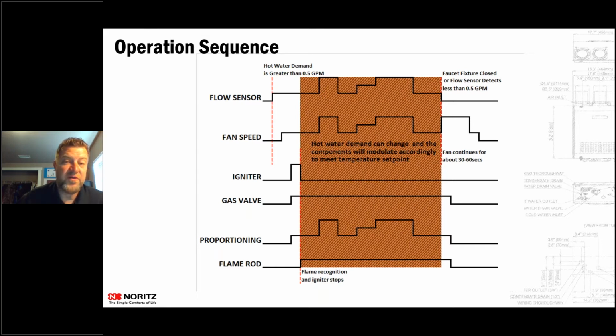tankless needs about a 30-degree differential to be able to fire and go. So if you have incoming water temperature above, say, 95 degrees, and a flow rate of half a gallon per minute, that unit might not fire, because if you're set at 120 and you don't have that 30 to 35 degree differential, that unit might look at that and say, I can't meet that minimum BTU requirement to fire. A lot of the older units would not fire.